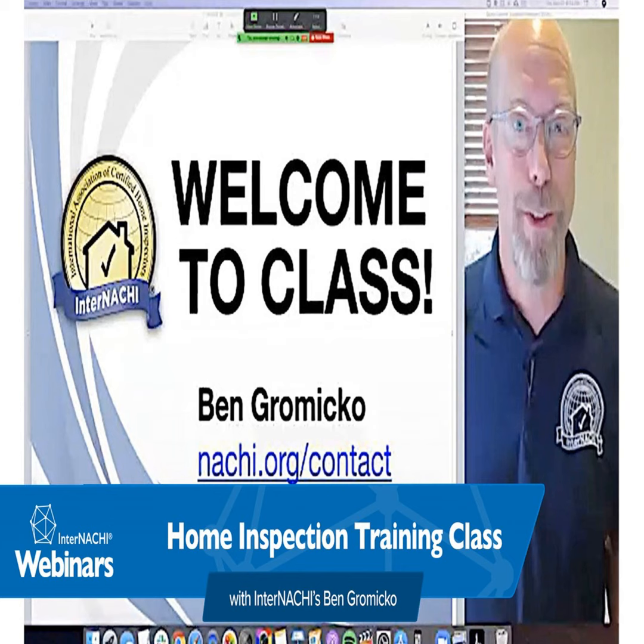And there's a garage entry door. I said entry door? Entry door. And there's the garage door. It's not manual. It's automatic. Has a garage door opener. It opens and closes. The inspector shall describe a garage door as manually operated or installed with an opener. So it has an opener. There's a normal operating control. There's the button there. It's plugged in. No extension cord. That's good.